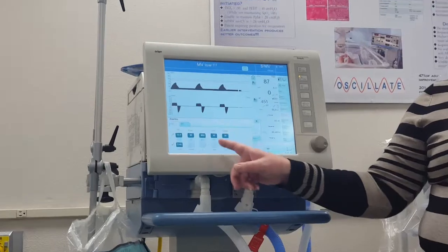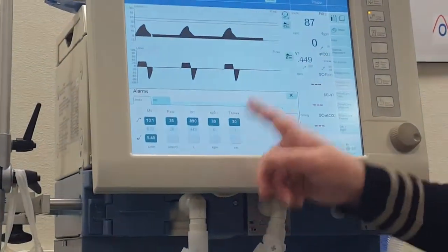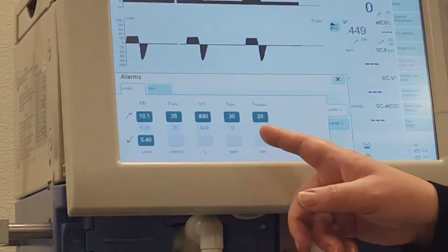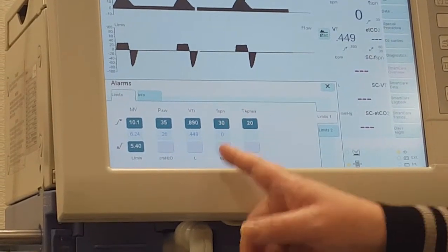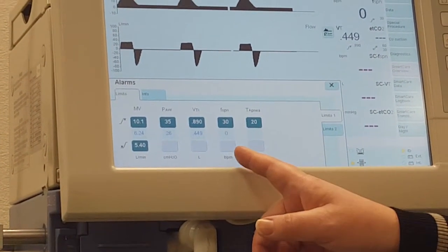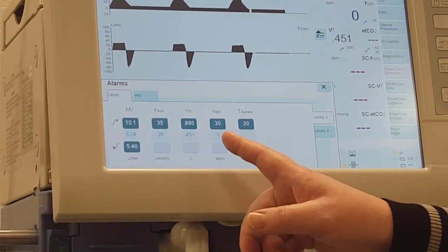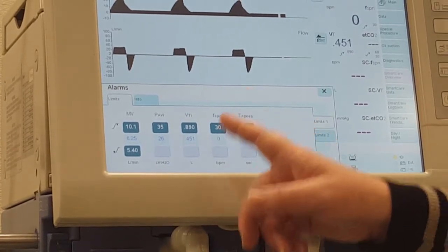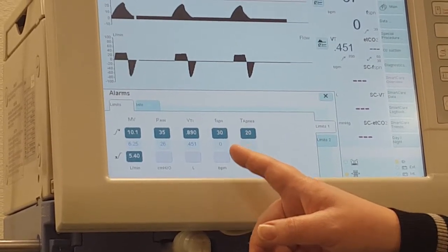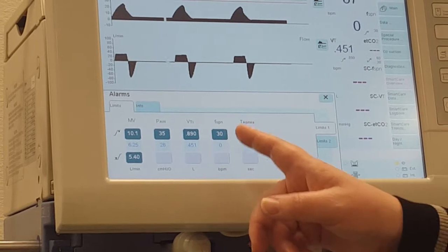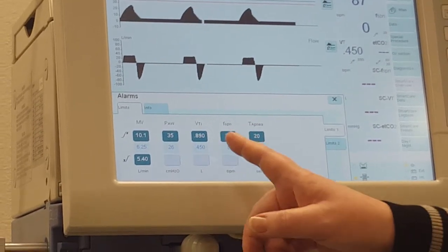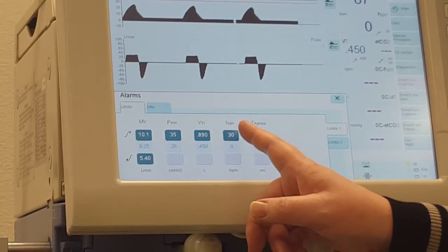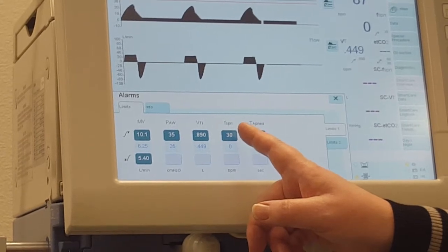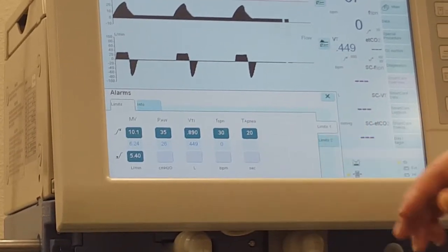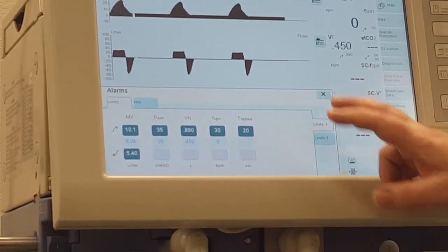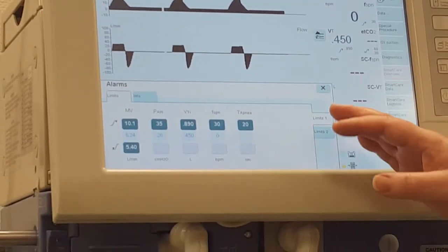So if the spontaneous rate goes more than 10 above the set rate, it will alarm. So it's only taking the spontaneous rate into consideration. So don't set it at 30. 30 plus 12 would be 42. We only want it to go 10 above whatever I'm set at. So on the DRAGER, the spontaneous alarm is set at 10. And then the apnea, something we'll talk about later. Okay, got me so far?